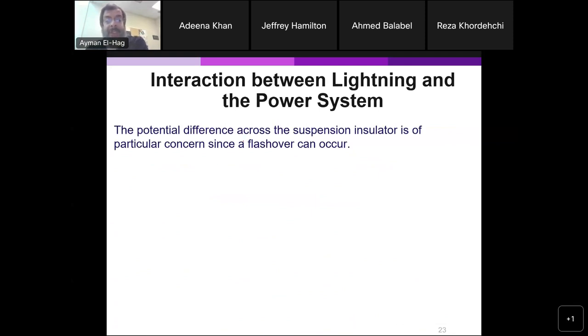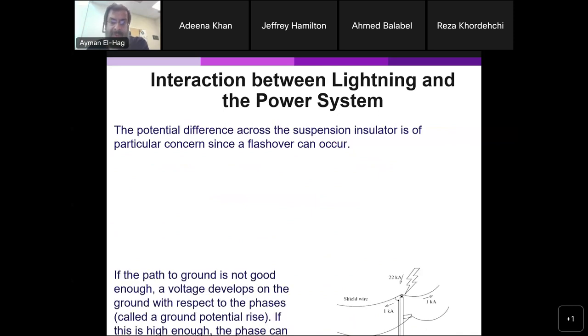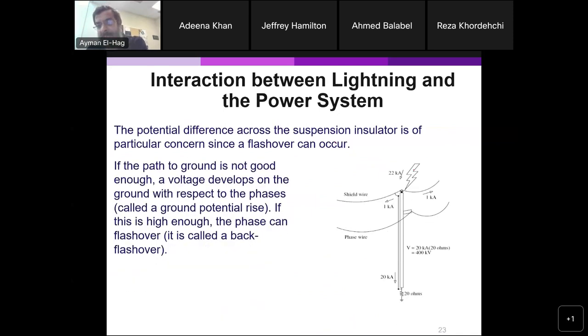Now, the potential difference across the suspension insulator is also of particular concern. How is that? Let's see here. We have lightning hitting the tower. Say 22 kiloamps hits here. 1 kiloamp goes to the right, 1 kiloamp goes to the left, and 20 goes down here. Most of the current goes down, and that's what we actually want. We want most of the current to be dissipated, not traveling. So assume that this happens.